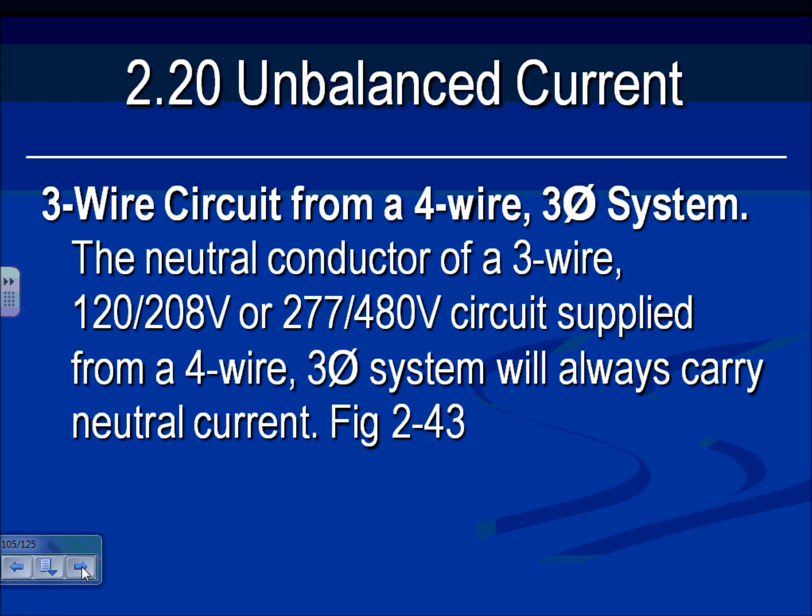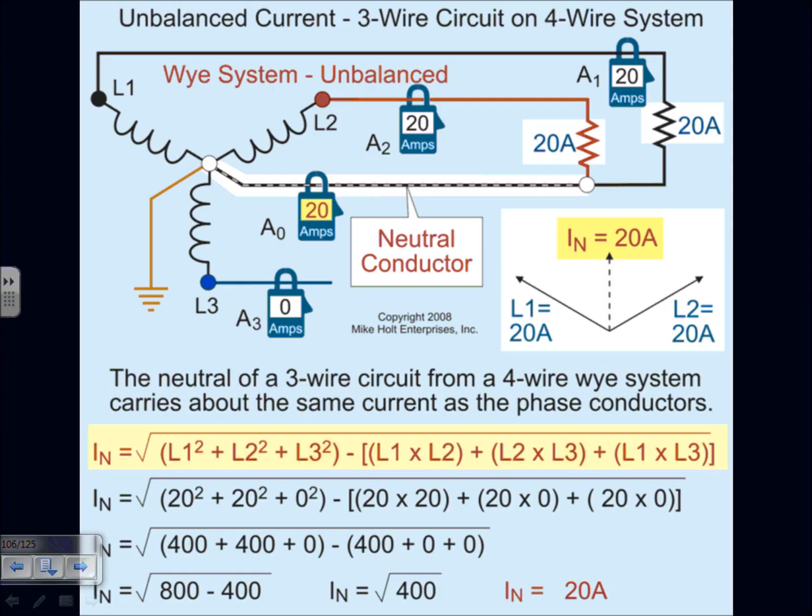They subtract each other's, as we said. And I'm going to keep going all the way to 277. Okay, now, this is where I want to just take a few seconds, guys. What happens if you have here's phase A, phase B, and phase C. Phase C is off, and you put a 20 amp plus 20 amp on phase A and B. It's a three-phase system. Have you guys seen the neutral formula to calculate the neutral for three-phase?